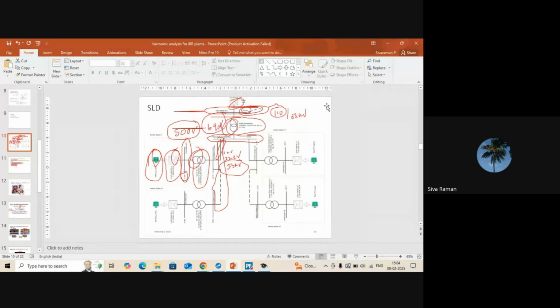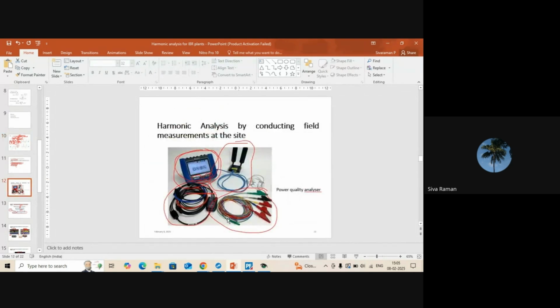And in the PT, the voltage is 110 kV by 110 volt. On the voltage side, a step-down transformer is normally used for the measurements. It will be connected to the 110 kV and its secondary voltage will be 110 volt. So we have to connect to the 110 volt, the CT and PT, and we have to modify the settings in this.